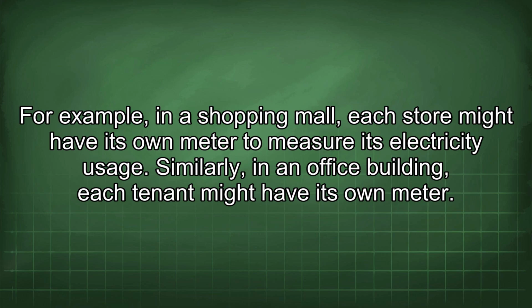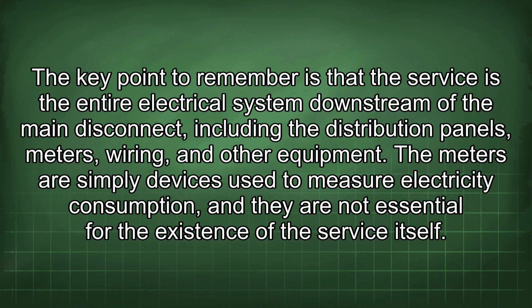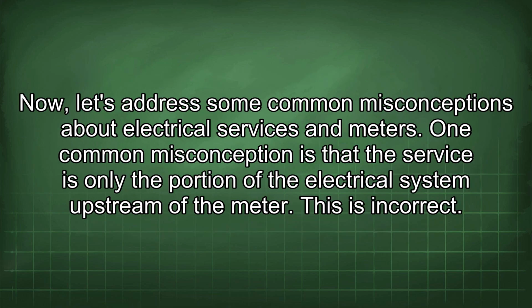For example, in a shopping mall, each store might have its own meter to measure its electricity usage. Similarly, in an office building, each tenant might have its own meter. The key point to remember is that the service is the entire electrical system downstream of the main disconnect, including the distribution panels, meters, wiring, and other equipment. The meters are simply devices used to measure electricity consumption, and they are not essential for the existence of the service itself. Now, let's address some common misconceptions about electrical services and meters.